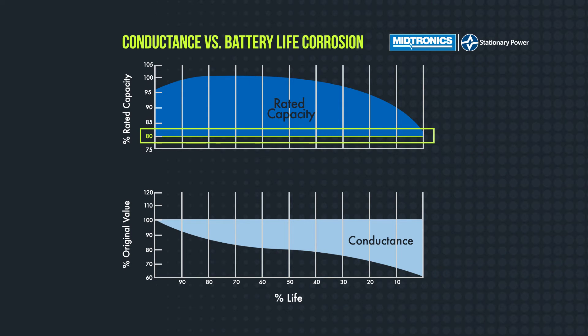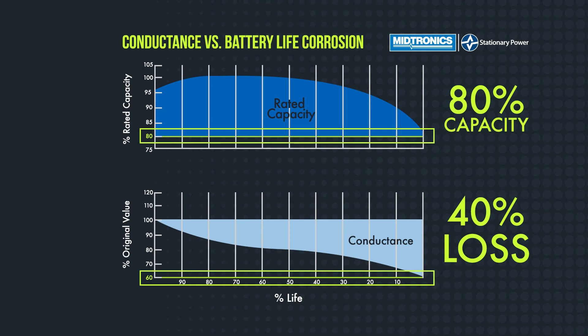Through Midtronics' studies over the years, we found that 60% of your baseline — the conductance value you measure when you first install a battery, which becomes your benchmark — when you get to 60% of that, so a 40% loss, is kind of equivalent to 80% capacity. It's a good rule of thumb to use when you want to know when you should start thinking about replacing your batteries: when you get to that 60% mark.